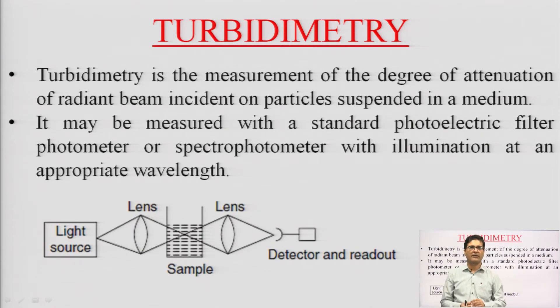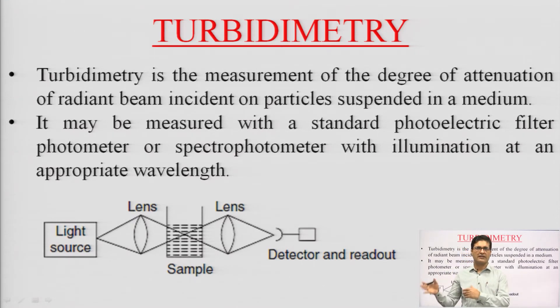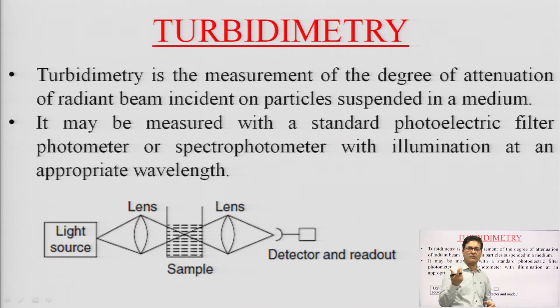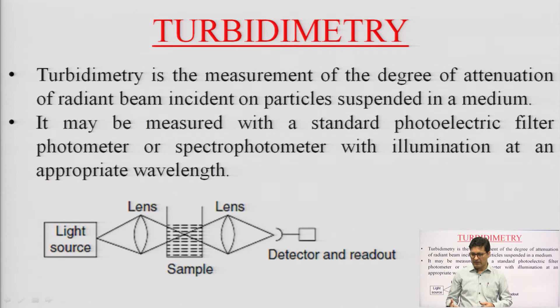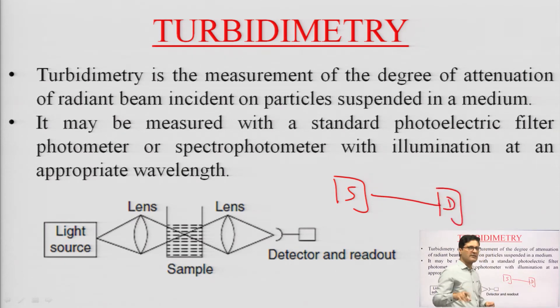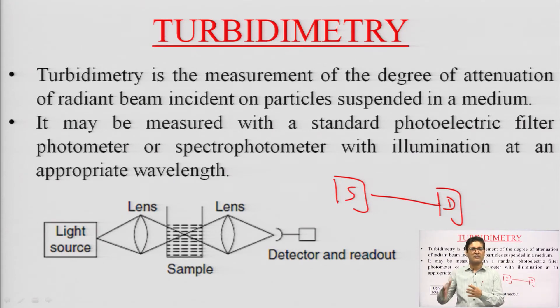On the other hand, in turbidimetry, we are not calculating the scattered light. Here, incident light strikes the sample, and after all losses — whether due to absorption or scattering — the transmitted light that comes out is determined. In turbidimetry we look at how much the intensity of incident light has been decreased. The arrangement is similar to colorimetric determination, with the light source and detector on the same axis. In nephelometry, the detector is at right angles to the source, whereas in turbidimetry they are in the same plane.